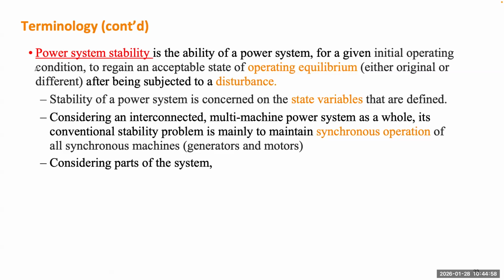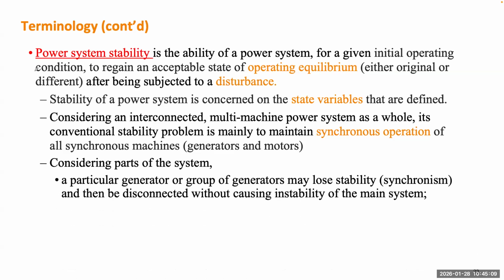Sometimes if you study a part of the system, because the system can be huge, but if you study only a single power plant with small generators, you may notice a particular generator or group of generators may become unstable, which means they will lose their synchronism with the rest of the system. But if that generator is not important to you, you can simply trip that generator, and your main system will keep the stability. So the question will be to either the operator of this local power plant or to the operator of the entire power grid.